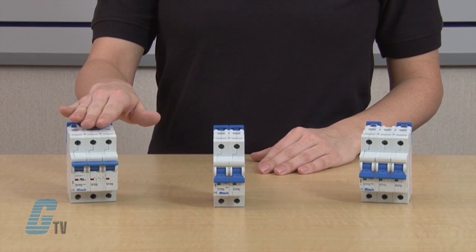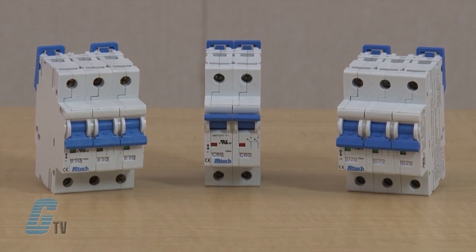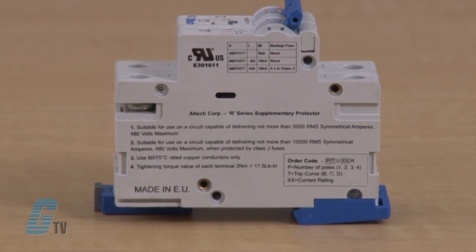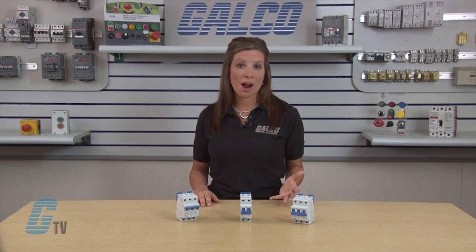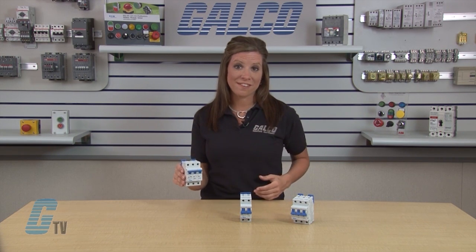Welcome to G-TV. Today I will show you Altech's R-Series Miniature Circuit Breakers. The R-Series of Miniature Circuit Breakers from Altech offer a compact solution to your protection requirements. These miniature breakers are UL1077 current limiting devices intended to provide supplementary protection within an appliance or other electrical equipment where branch circuit protection is already provided or is not required. The R-Series Circuit Breakers are DIN rail mounted devices and can offer a good equivalent to fused systems.